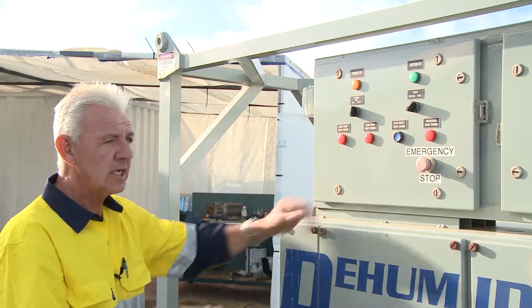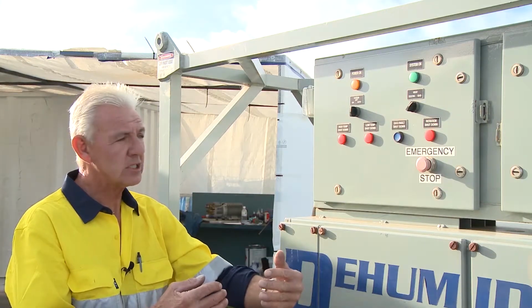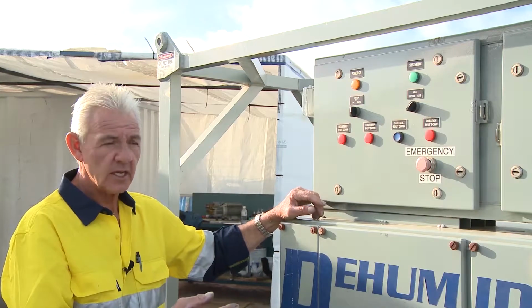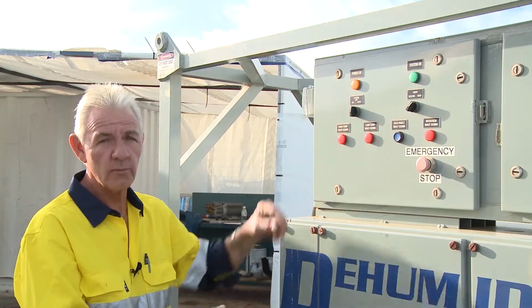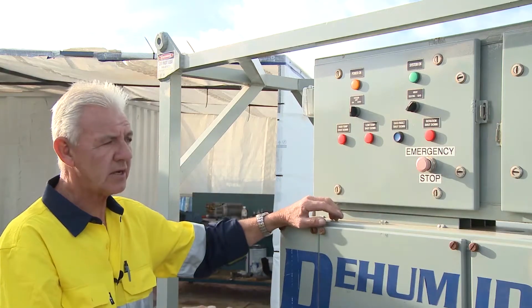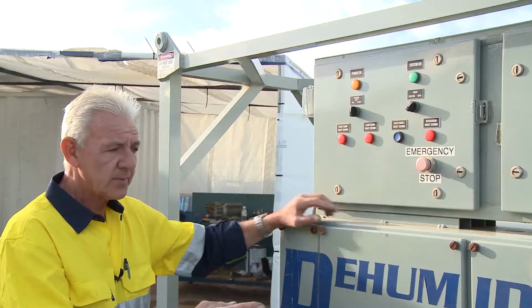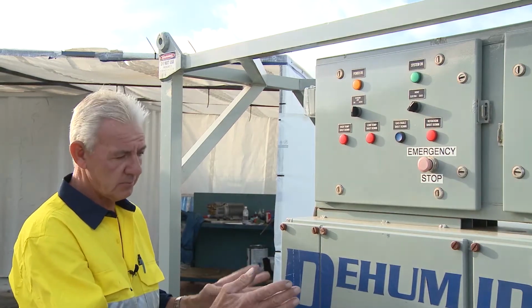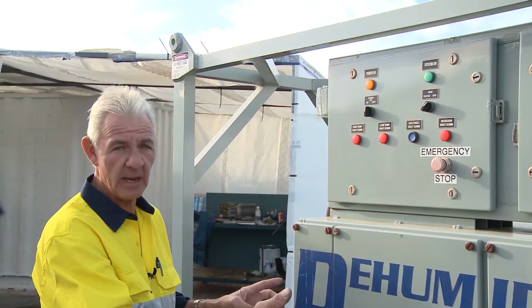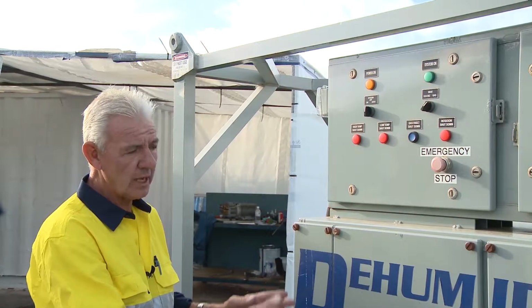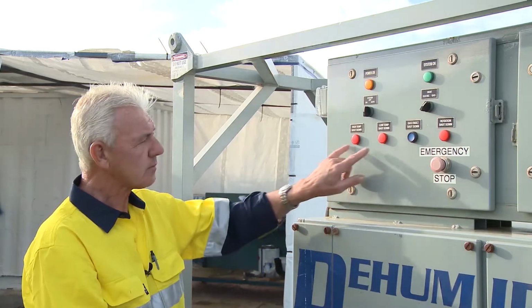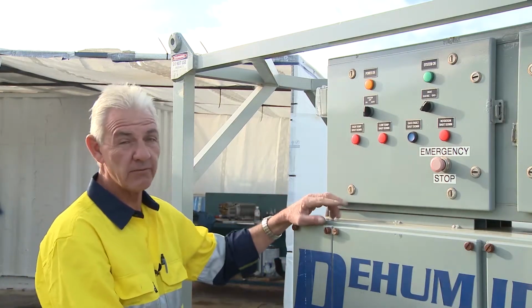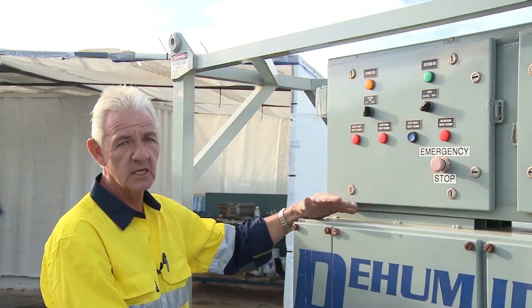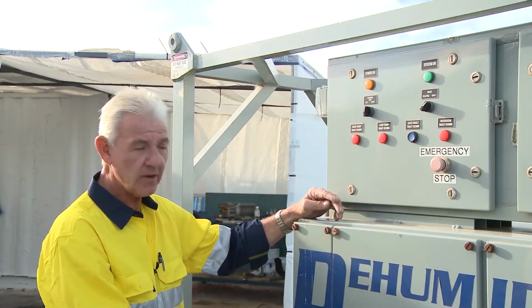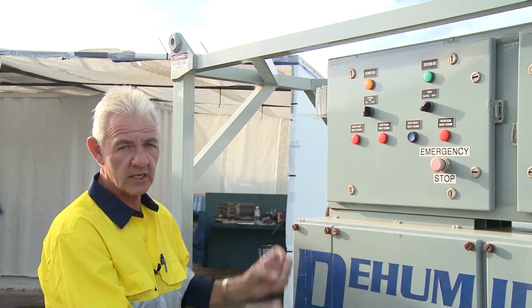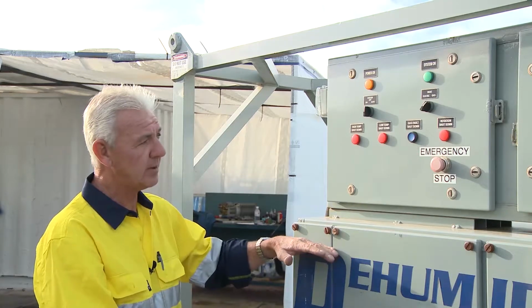The low temperature shutdown is on the other side of that scale. So if, say for example, we have an influx of air and it can't cope with that volume of cold air, you'll have a low temp shutdown. Predominantly that is just a safety measure to keep this particular desiccant wheel and its heating capacity at a reasonable level that the machine can monitor. So is it a common occurrence? No, it's not. It's just a fail-safe in relation to what is processed as far as the air is concerned. The cubic metres of air that's travelling through the machine is monitored hot and cold. So peak high or low, this will pick it up.